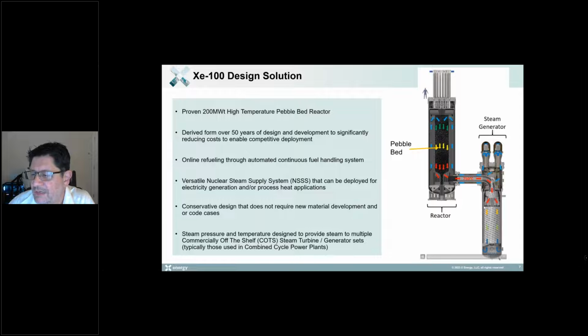It then passes through a helical coil steam generator. This is a once-through steam generator with the water flowing in at the bottom. We preheat and superheat the steam in one pass, and get a high outlet temperature on the steam of 565 degrees C, which is similar to what we get on high efficiency coal-fired power plants. And that allows us to really utilize off-the-shelf steam turbine generator sets. So X-Energy didn't design any steam generator or steam turbine generator set. We're buying this off the shelf from multiple vendors that have that size of turbine.